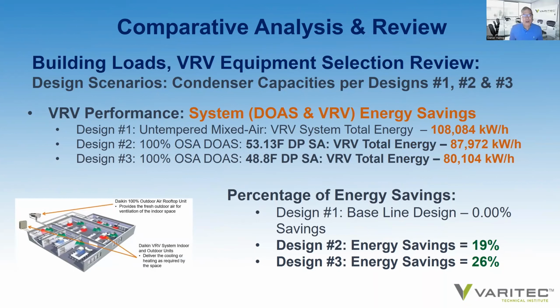What does it mean with regard to energy? Well, design system number 1 required 108,000 kilowatt hours of annualized energy consumption. Design number 2, supplying 53.13 degree dew point air, had 87,972 kWh of consumption. And design number 3, supplying 48.8 degree dew point air, offered even greater efficiency at 80,104 kWh. And by the way, these values not only include the variable refrigerant system, but also the DOAS unit, including the fan energy in the DOAS unit.